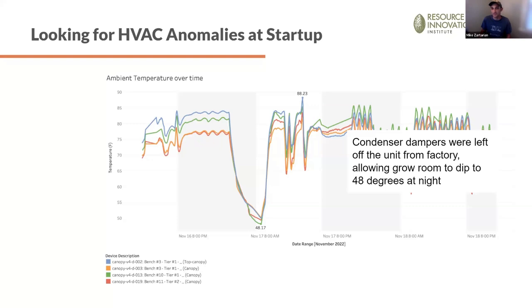Sometimes the systems light up and play, they work, and the folks commissioning them say, 'Oh great, they're working, they've held set point for an hour, we're done.' But what we've found is you have to watch the system closely and test it through all conditions over a period of time. That's why I say a couple weeks is really great to have for this.